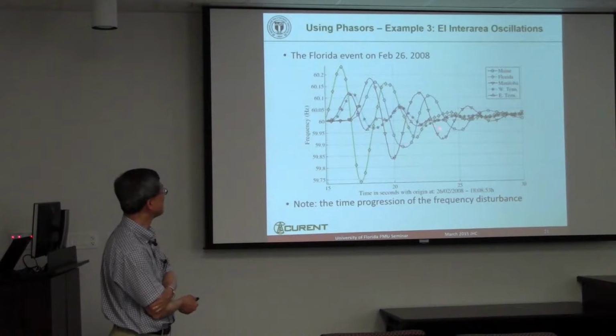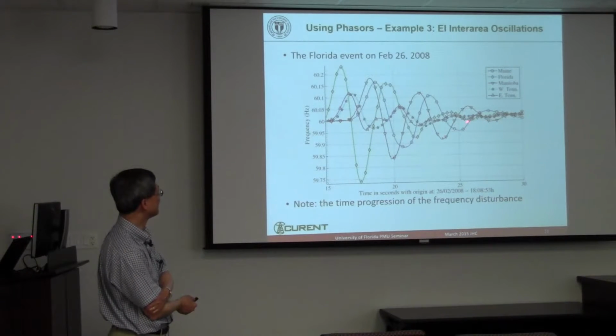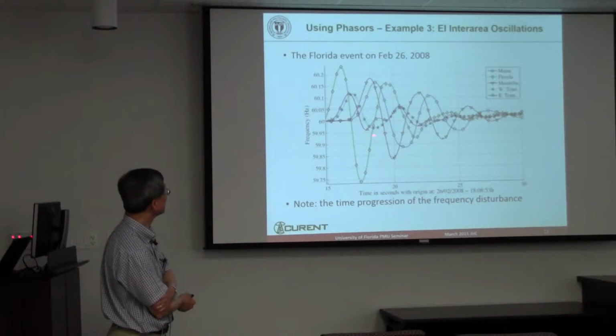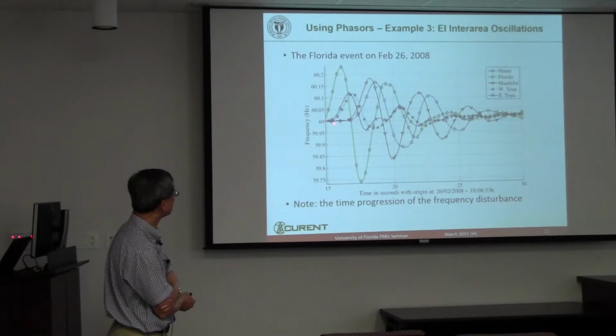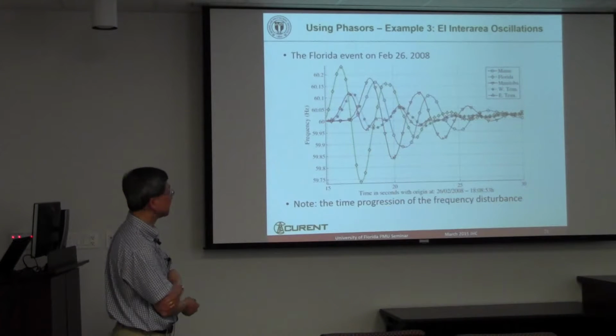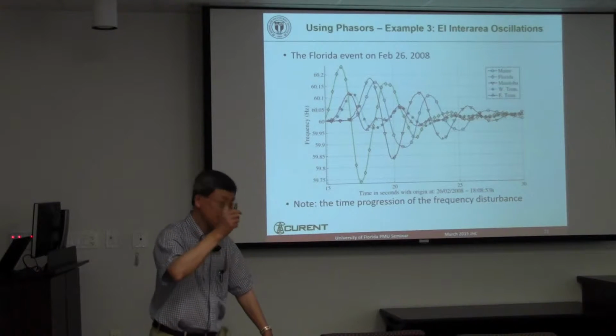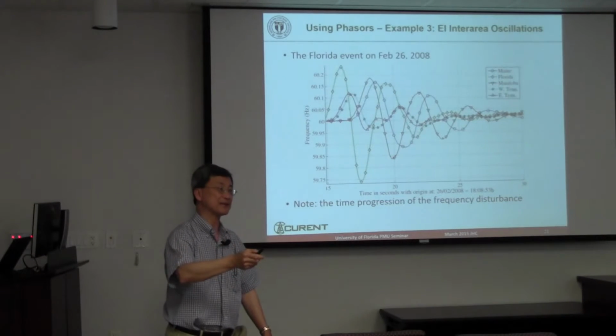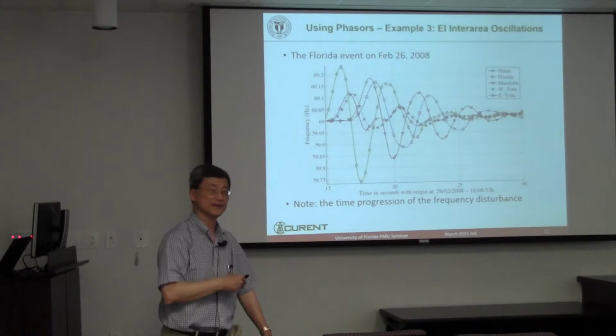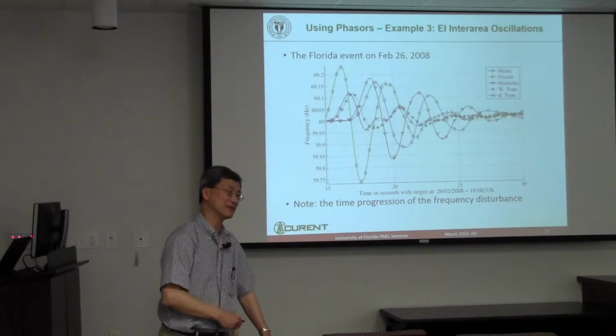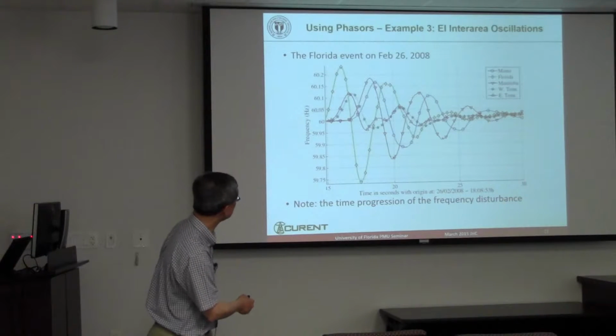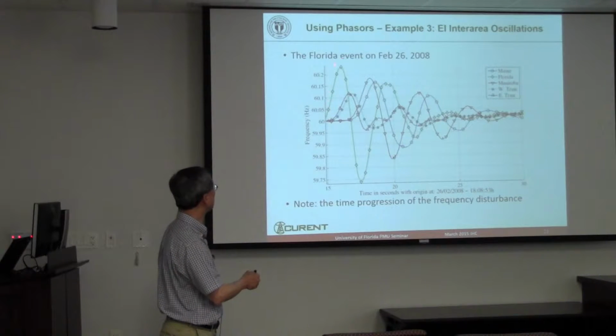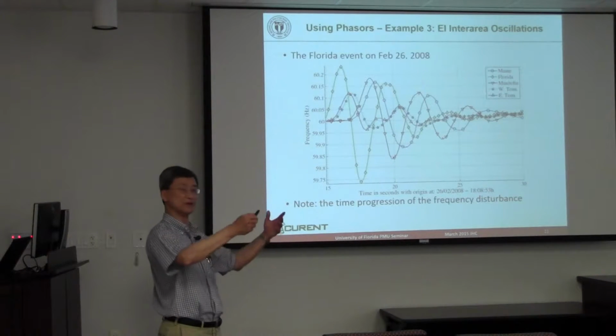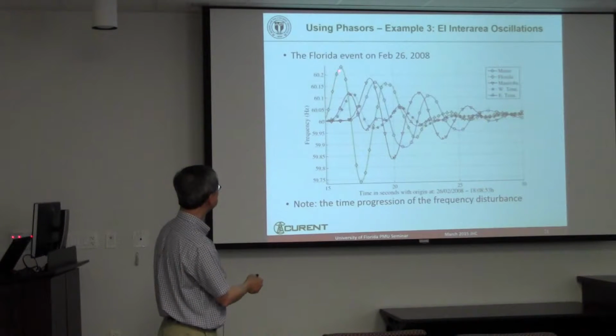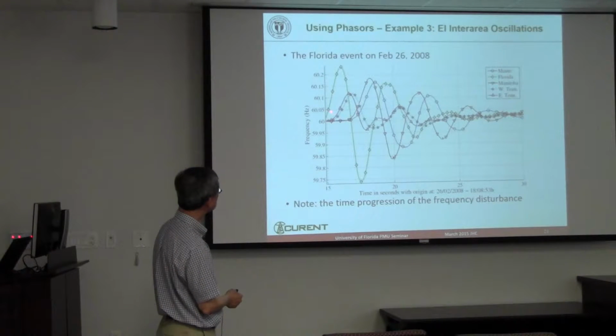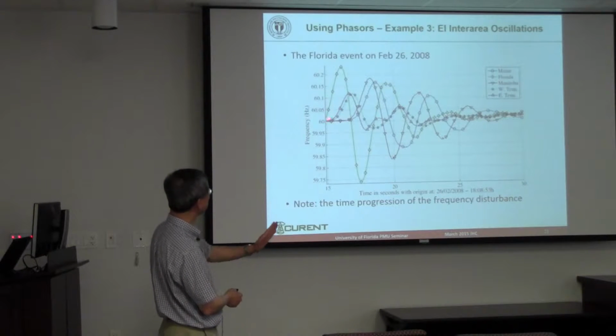This is actual phasor measurement data from PMUs. The event is that the nuclear power plant tripped, and as a result a lot of loads were tripped — more load than generation was tripped. So in Florida, the frequency initially rose just because there was more generation than load, and this frequency rise propagated to the rest of the system.